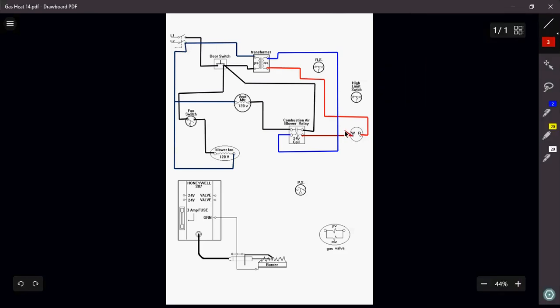So out of my W, and I'm just going to come right here, just to make it a little neat for everybody. I'm going to come out. I'm going to come right into each one of these switches in series with each other, one right after another. My rollout switch, I'm going to come out. All right, going to come down. And out. So, I'm at my pressure switch. Where do you think my connection should be in this diagram? If you said the ignition module, the Honeywell ignition module on the 24-volt connections there, you're absolutely correct.